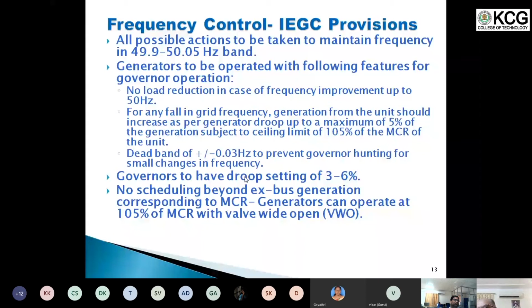So that 5% of VWO condition is available to provide the primary response in case of any requirement. Let's say, if a big generator trips because of any problem with that generator at any point of time, now there will be a deficit in the system of the megawatts, and then this will cause those generators to initially slow down.